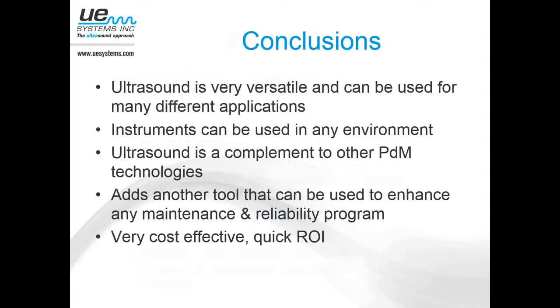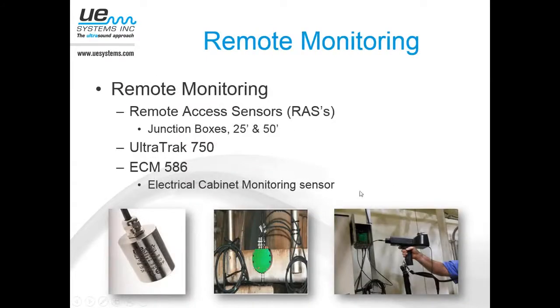Are there any options for continuous ultrasonic monitoring and trending on bearings so that alarms can be set up as levels increase? We can do it either with the switch box, using your standard handheld tool, or you could set it up with an UltraTrak 750. But typically, the online monitoring we're doing is still more of a monthly trending type of thing.